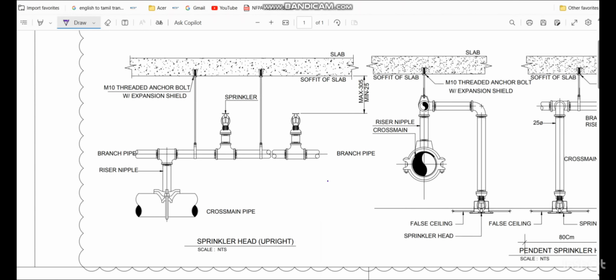Now we are going to see the installation details for the project, and additionally I will explain some important installation mistakes which we normally make on site. So the first installation detail you can see here is for the upright sprinkler installation. We have the cross main pipe. From the cross main we have the riser nipple which is taken up, and from here we have the branch pipe. So we have the sprinkler line.